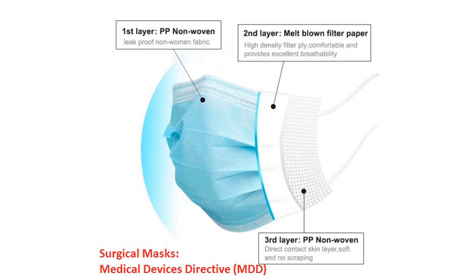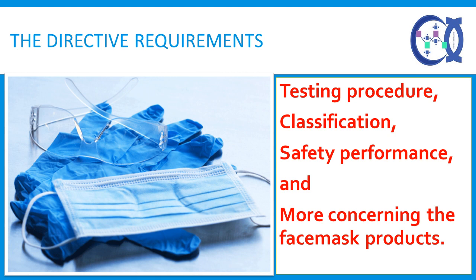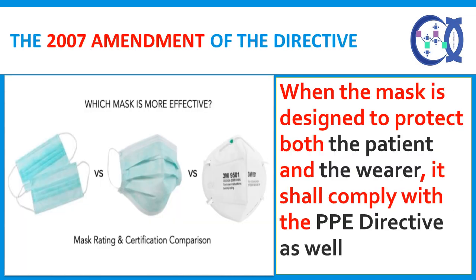Surgical masks. The Medical Devices Directive, MDD, applies to medical devices to be placed in the EU market. As such, surgical masks, which are mainly designed to protect the patient, fall under the scope of the MDD. The directive sets requirements for face surgical masks such as testing procedure, classification, safety performance and more concerning the face mask products. Surgical masks are classified as a Class 1 medical device. However, if your masks are sterile, then they are classified as Class 1, sterile. Also, note that according to the 2007 amendment of the directive, when the mask is designed to protect both the patient and the wearer, it shall comply with the PPE directive as well.